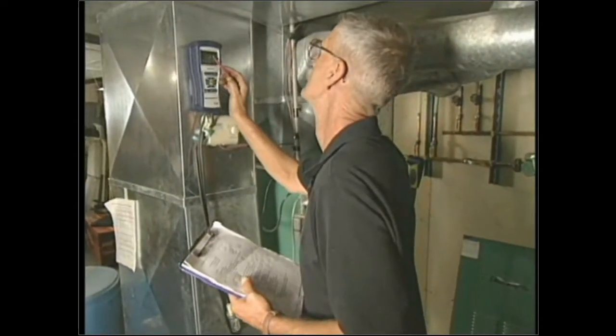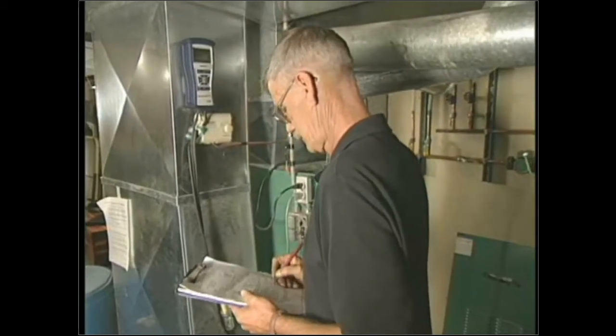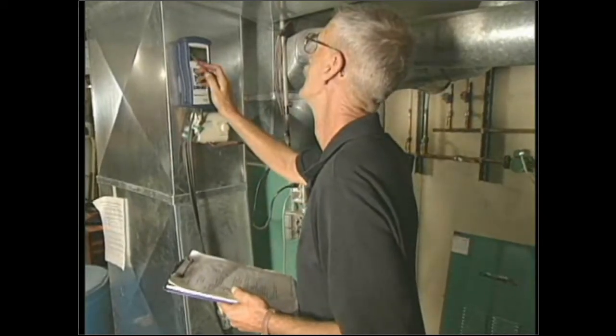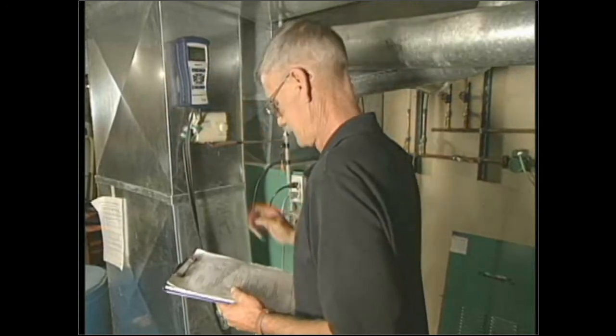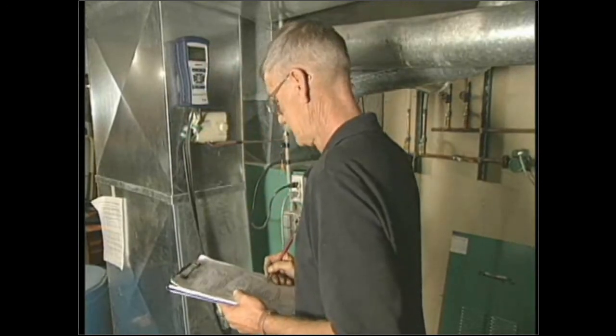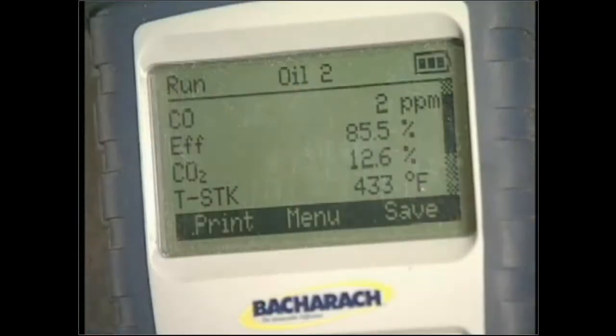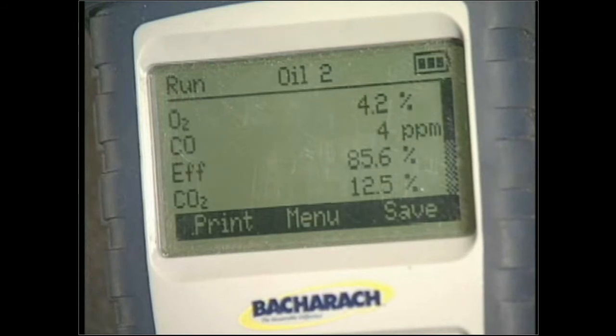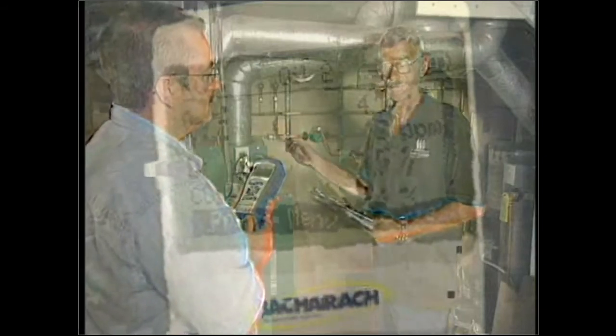As an auditor, you're taking all those readings, documenting them, and then comparing those findings to the PMI. Yes, we compare it to what the unit should be producing. The efficiency reading has to be within a certain bracket for our programs. The stack temperature is a number that is used in that calculation. The oxygen we need to be between about 4% and about 7% or a little higher. But the big one is the CO. We want to measure CO just like we do on all the other appliances. And we're fortunate on this one, it's running about 3 parts per million. Good news for the homeowners. Very good news for the homeowners.